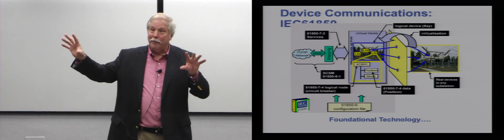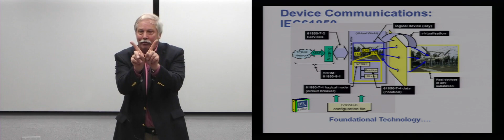So what often happens is I have a phasor at one end of the line and a phasor at the other end of the line. If the systems are isolated, which happens sometimes, the phasors will be rotating. For example, let's say you have a factory with its own generators, and then the power system has generators - the two will not be synchronized. What will happen is the two phasors will be rotating at some angle relative to each other.